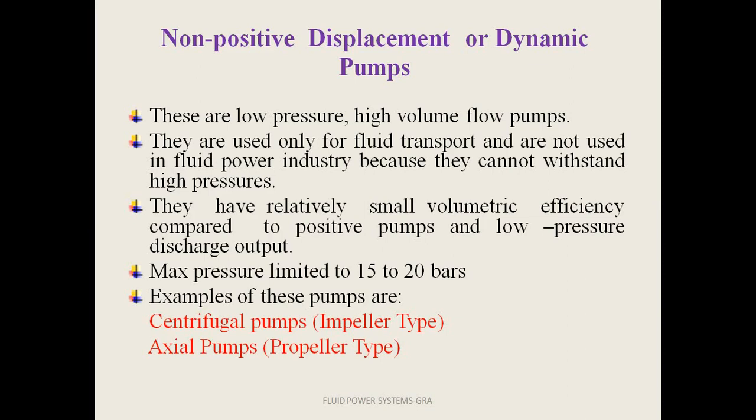These are specifically used to transport the fluid from one place to another, and these cannot be used in the fluid power industry because they cannot withstand high pressures. It is just used to transport the fluid or to lift the fluid from the lower tank to the overhead tank. They have relatively small volumetric efficiency compared to positive displacement pumps and have low pressure discharge output.